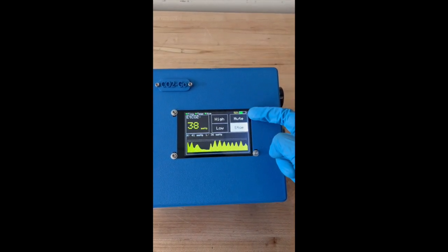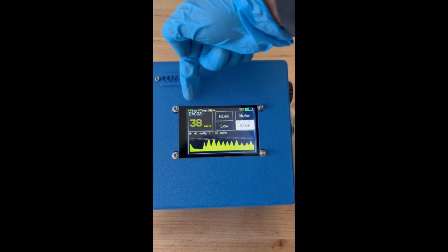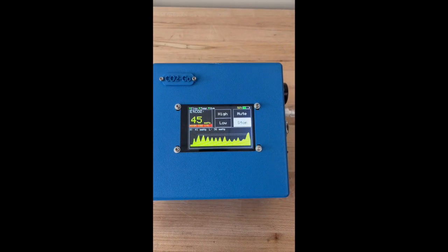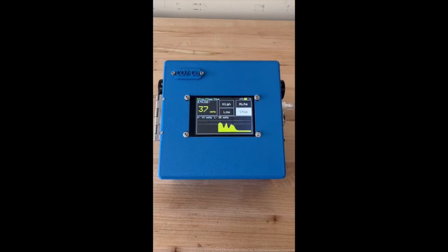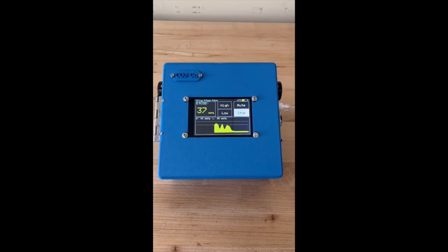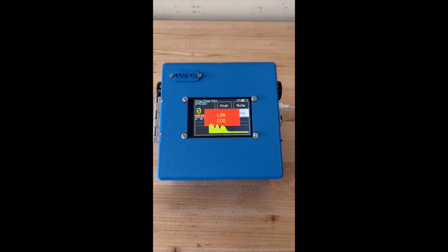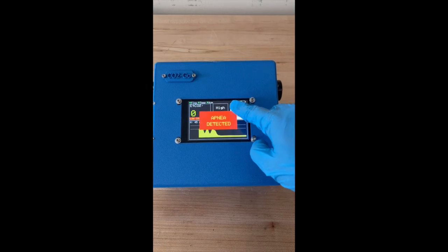On the graphical user interface, we have several other indicators as well: charging, humidity, temperature, and flow. It lets you know if there's any issues with any of those, whether you need to charge it, or if there's condensation issues, temperature issues, or if flow is blocked. The decibel volume was reduced for this video, but these alarms can be muted with the mute button, and they alert healthcare professionals to the breathing levels of the patient.